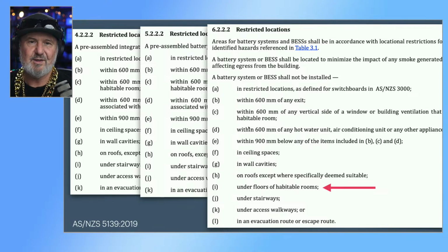But it's the fairly obvious ones: bedrooms, lounge, kitchen, study, places where people spend extended periods of time. And non-habitable rooms are things like garages, utility rooms, laundries, walk-in wardrobes. I know that's a funny one. You can't put a battery in a bedroom, but you can put it in the walk-in wardrobe. But there's still some requirements about clearances from a doorway, 600 mils. So it's got to be a big enough walk-in wardrobe that you can get the battery away from the door. But there you go. Section 6, not under the floors of habitable rooms.